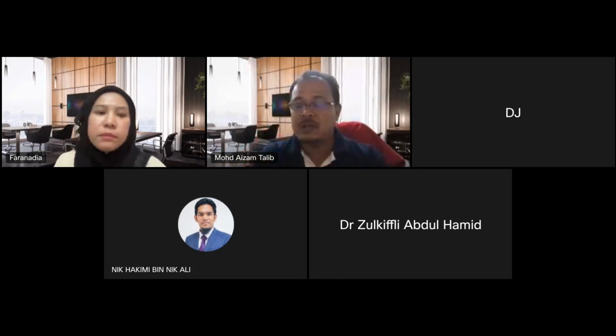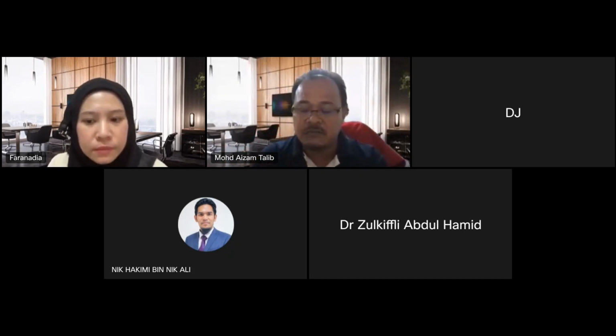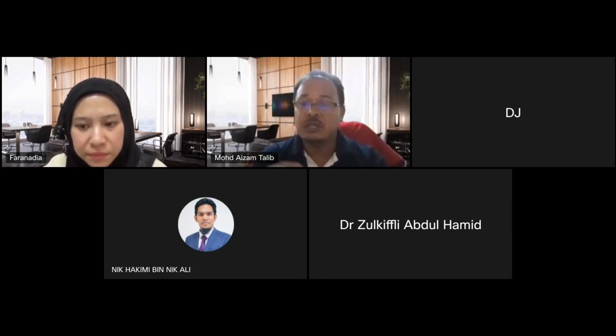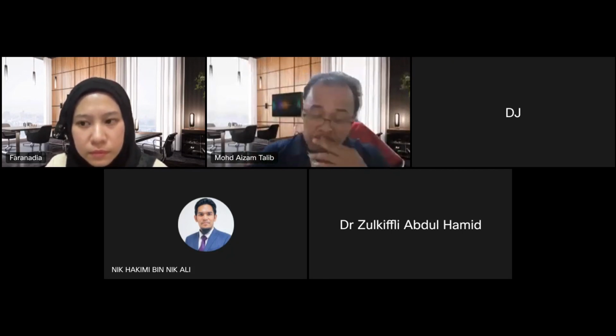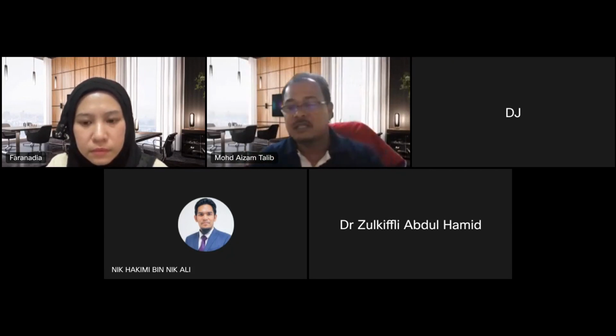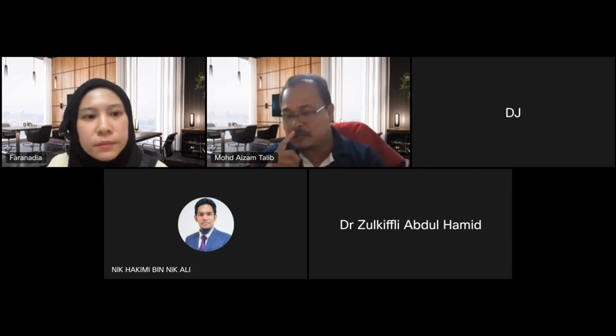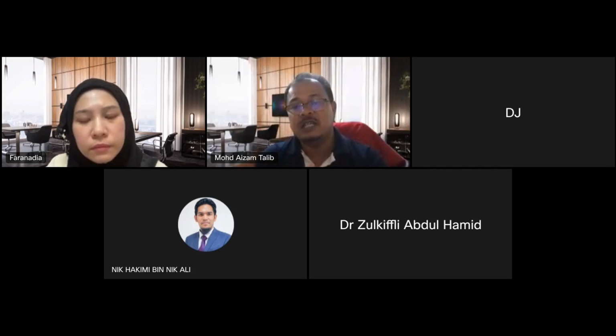But for locating, because TEV, UHF, and HFCT are not able to pinpoint the location of the fault or the PD activity in the test object, we need to use acoustic. With acoustic, we put different sensors around the test object, and based on the arrival of each signal at the sensors, we are able to pinpoint it. So my answer is, it depends on the situation and the application.